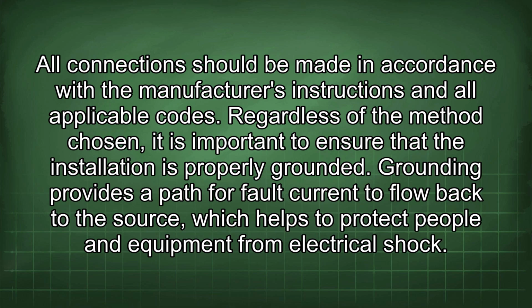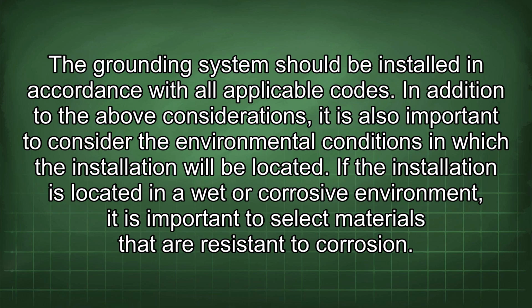Regardless of the method chosen, it is important to ensure that the installation is properly grounded. Grounding provides a path for fault current to flow back to the source, which helps to protect people and equipment from electrical shock. The grounding system should be installed in accordance with all applicable codes.